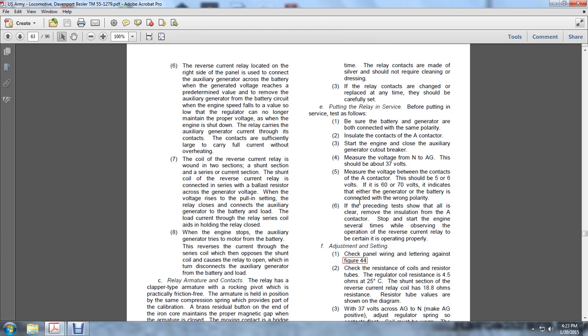The relay carries the auxiliary generator current through contacts sufficiently large to carry the full current without overheating. The coil of the reverse current relay is wound in two sections: a shunt section and a series current section. The shunt coil of the reverse current relay is connected in series with ballast resistors across the generator voltage. When the voltage rises to the pull-in setting, the relay closes and connects the auxiliary generator to the battery and load. The load current through the relay series coil holds the relay closed.